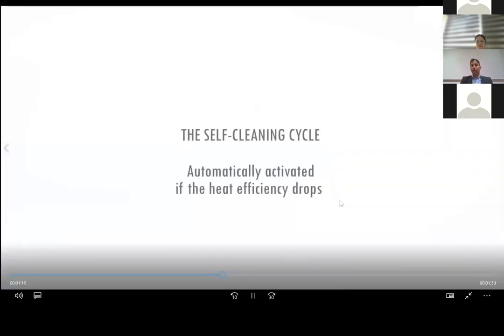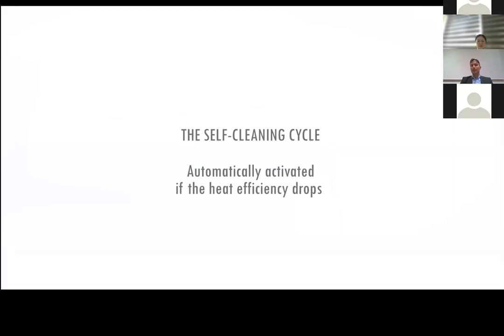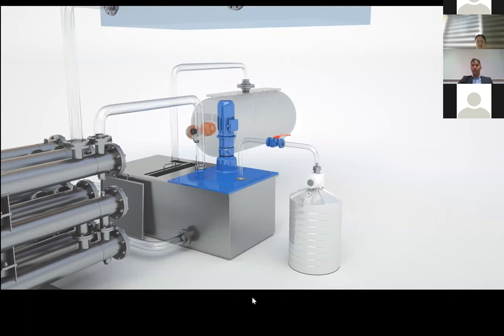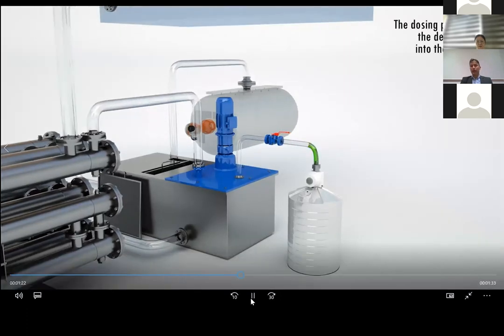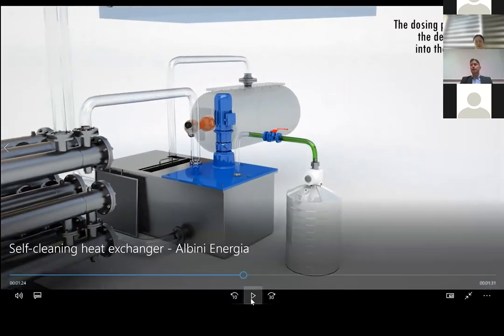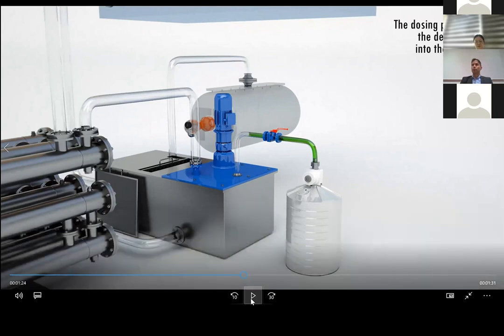That's the core of the system, so the acid self-cleaning cycle. When the efficiency drops, we have some sensors, flow meters, and temperature probes in order to calculate and monitor the energy efficiency of the heat exchanger. When it drops, the heat exchanger goes to a bypass system and the cleaning procedure starts automatically.